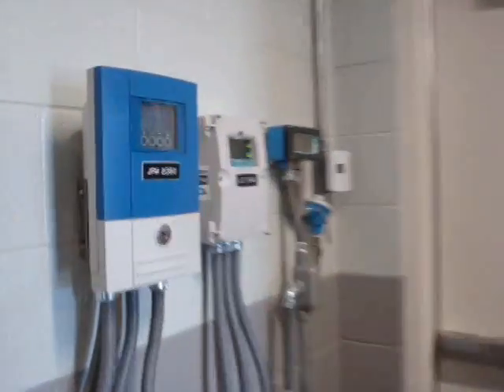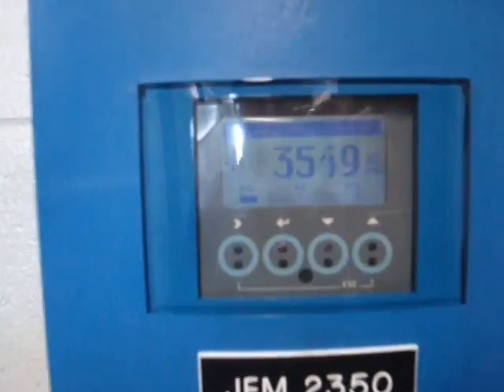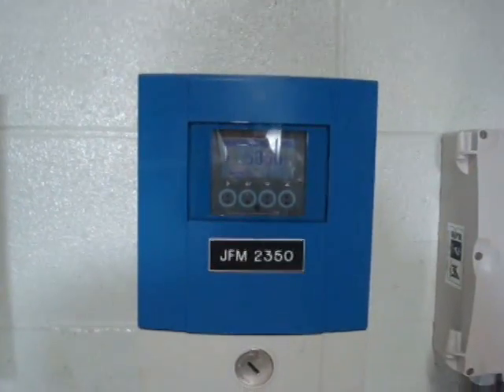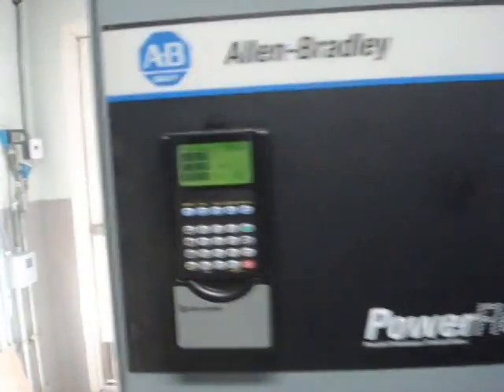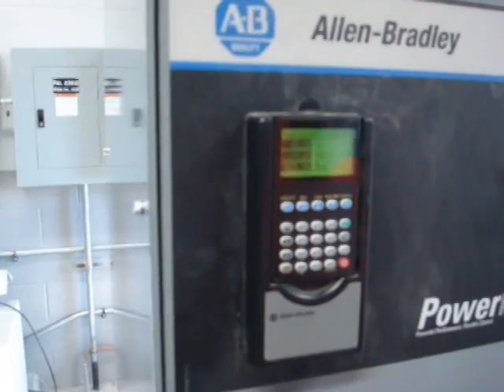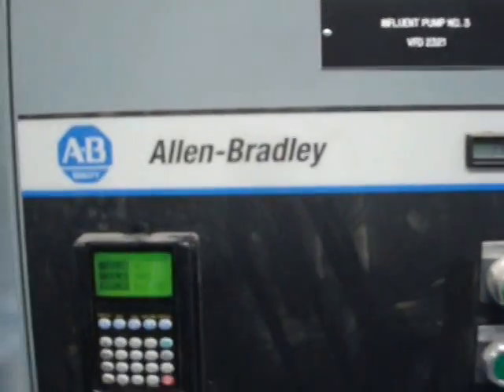Starting with each of the pumps, we follow the flow test report in order to verify flows. What we're looking at here is the result of testing the 2 lower horsepower pumps. We repeated each of the processes until we'd filled out the entire report. It showed that from 30 through 60 hertz for each of the pumps, it produced the flow in gallons per minute that was expected, as specified. 5,500.